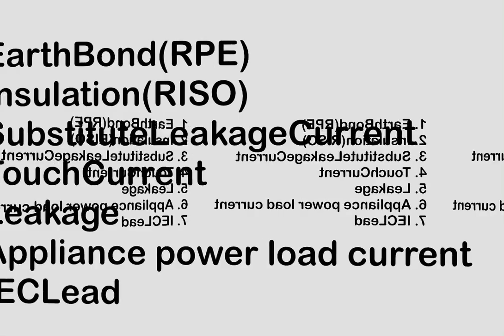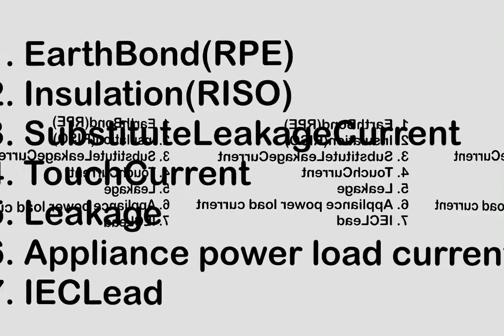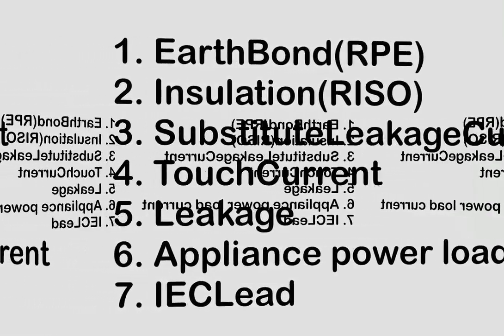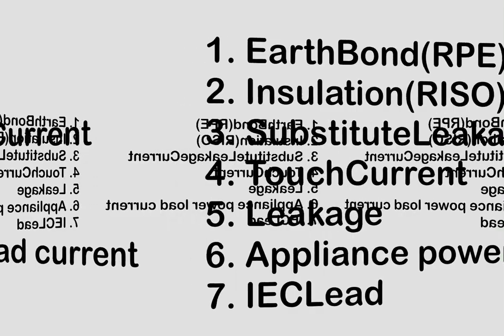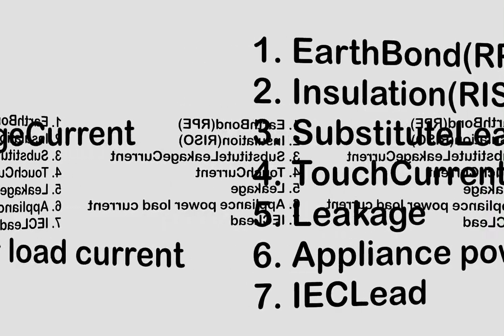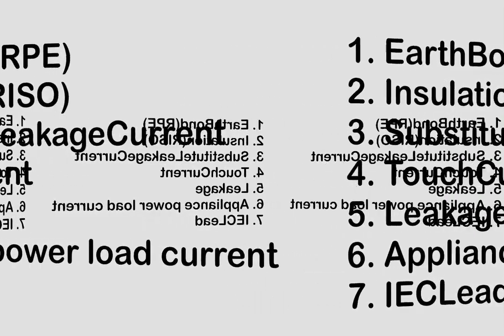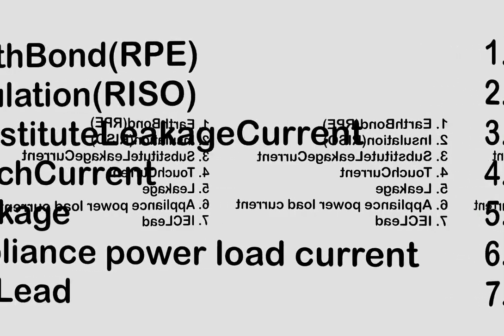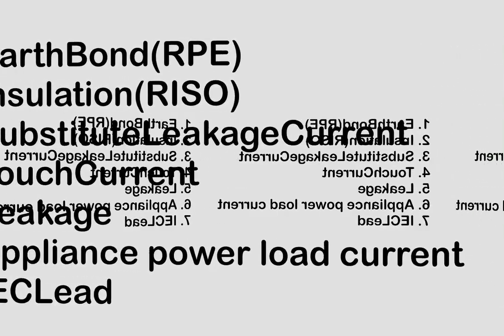The insulation test determines how effective the dielectric — that means the insulation — is in resisting the flow of electrical current. Third, we need to carry out the substitute leakage test. This applies a reduced AC voltage, typically 40 to 60 volts AC, between the line and neutral joined together and the earth conductor or test lead for Class 2 equipment.